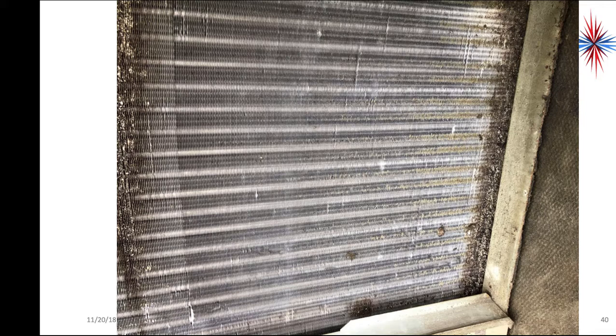This is a restaurant, there's grease around. Okay, so you'll notice the evaporator coils have a lot of grease buildup on the outside. In a restaurant where there's grease buildup, there's usually salt, and this is an aluminum evaporator coil.